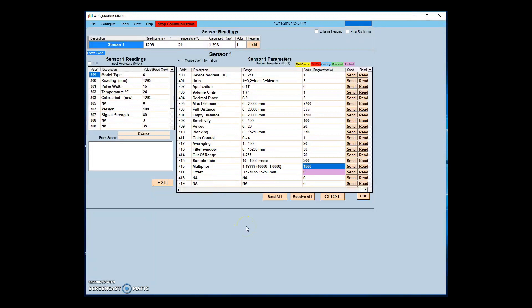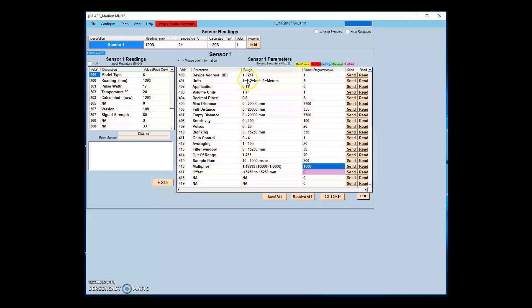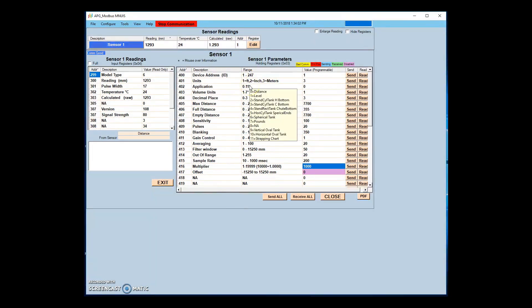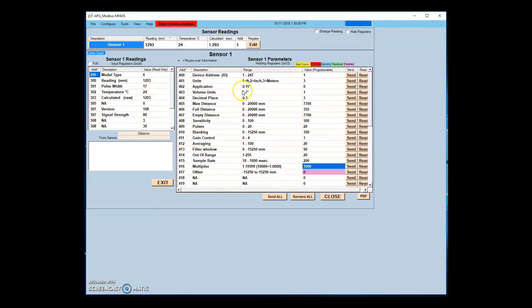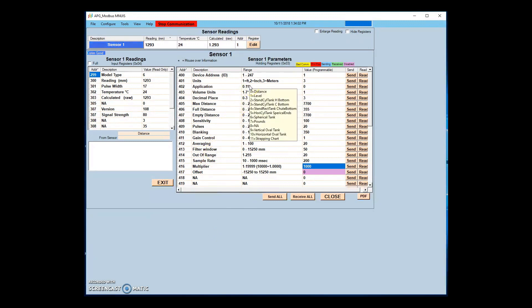The application type determines how the sensor will calculate readings. If type 0, 1, or 7 are selected, the readings will be calculated using distance mode. If type 2 through 6 or 9 through 11 are used, the readings will be calculated in volume mode. The volume unit parameter sets the unit of measurement the sensor will use to display readings if set in volume mode. Application types 2 through 6 and 9 through 11 are calculated in volume mode.